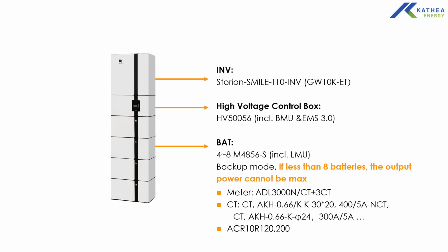And then just under the inverter, we have what you call the HV box, which is the high voltage control box. On this box, that's where all the terminations are done, and that's basically the management system for the whole system between the inverter and the batteries. So this unit is detachable from the inverter, unlike the SMART 5. All your battery cables, all batteries are connected in series up to 8 modules. The battery is 48 volts, 56 Ah, like 51.2 volts nominal voltage. So all of them are daisy chained, put in series, up to 8 batteries.